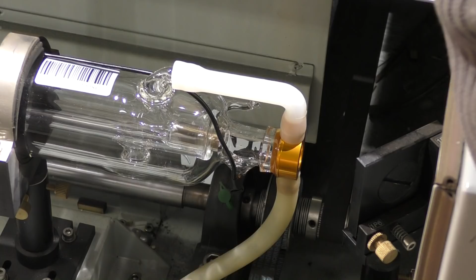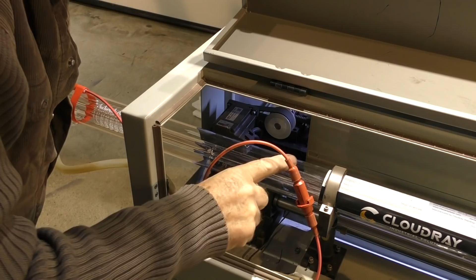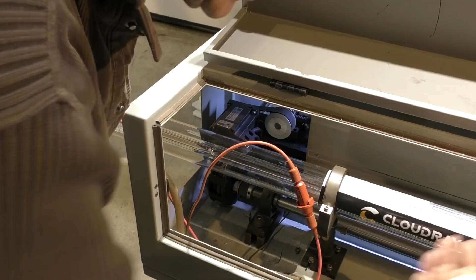There we go. Lots of bubbles. I'm just checking along here and I can't see any bubbles. There are one or two very small micro bubbles sitting on the top, right on the top surface of the tube, which I don't think will cause any problems at all, because they're on the top side of the second tube in. They're sitting on the top of the water jacket. They're not affecting the heat transfer from the ionisation tube into the water jacket itself.